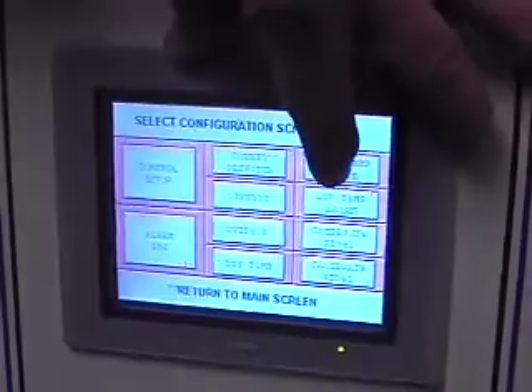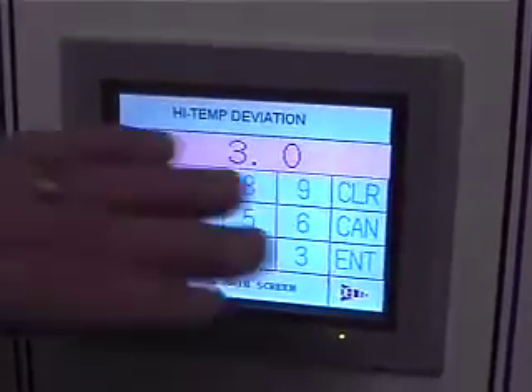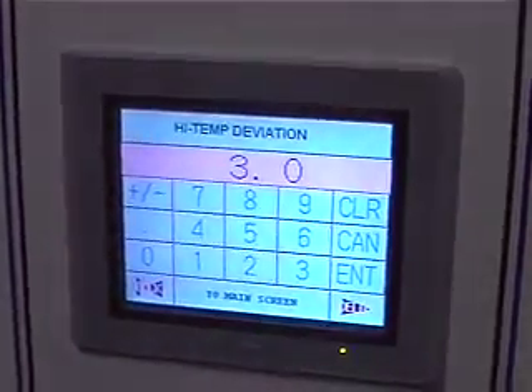The problem with heating the coil up is then you've got to cool it back off, and you get delays and all these things. It's an overcomplicated system that doesn't ever need to be there, and that's what we found out in the last 25 years anyway. The alarms, we'll hit the alarms real quick while we're at it. They're both going to look the same. Alarms are handled as deviation from set point. So if you change the set point, and you're okay with the deviation, you don't have to change the alarms.